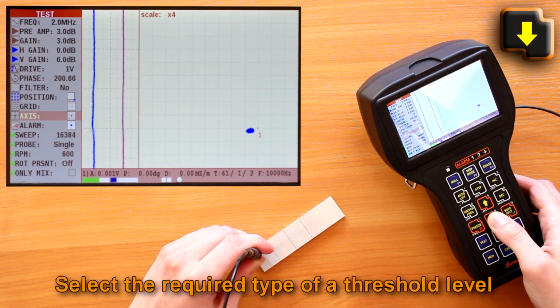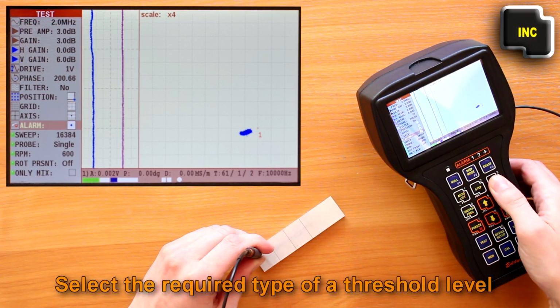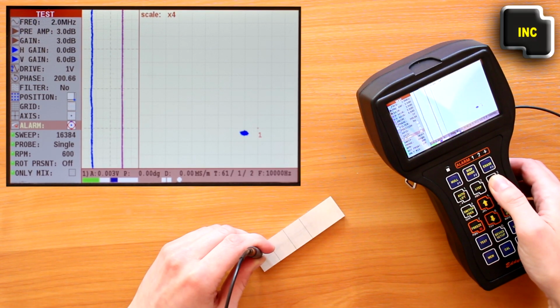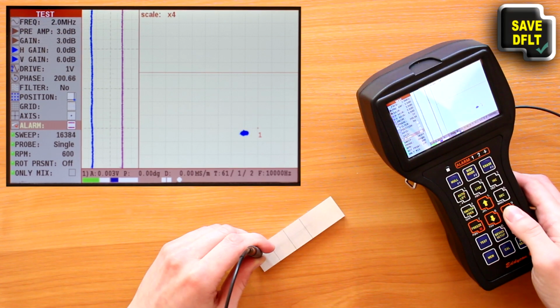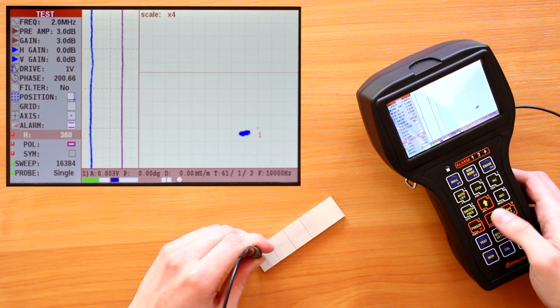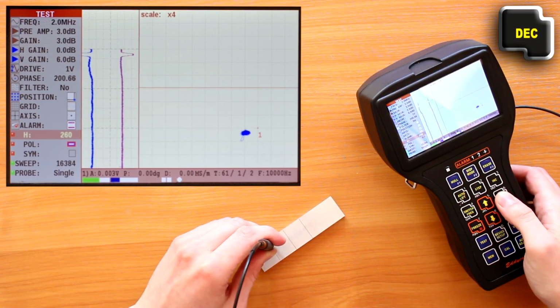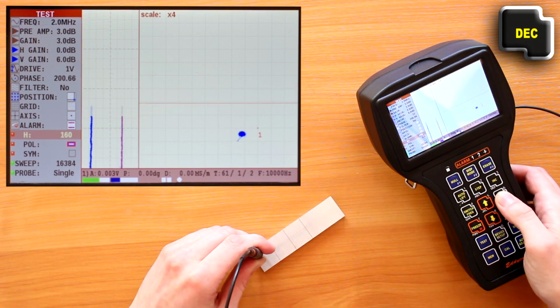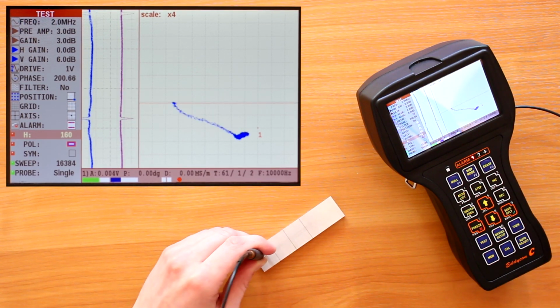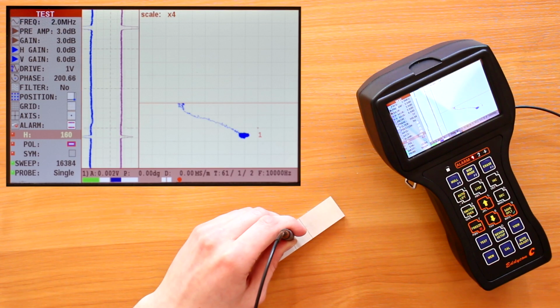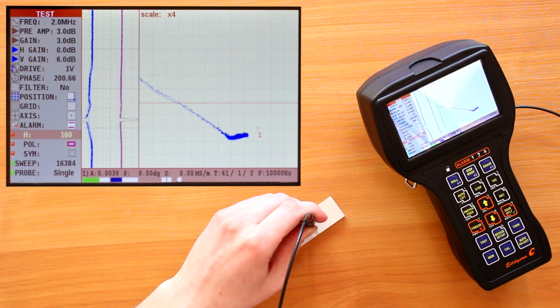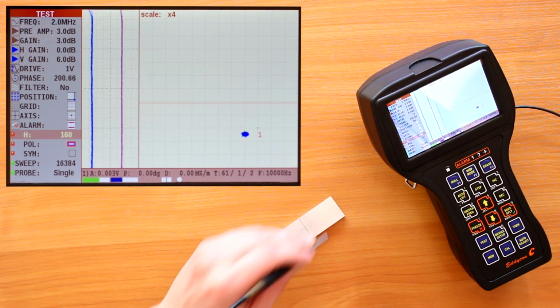Select the required type of threshold level. Move the probe across the artificial defect of a calibration block several times and visually set up the alarm relative to the signal from the defect. After performing all these steps, the setup procedure is considered to be completed.